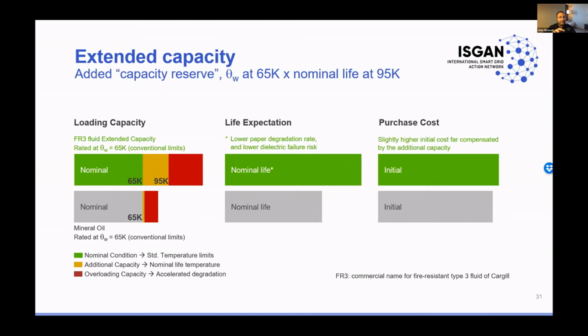The important point here is, as Angelo mentioned, the assessment of the losses in the transformer life considers nominal rated capacity, but the transformer is always dynamically loaded, and a typical average loading will be much lower than 100%. So when we expand the loading capacity, we can increase the average loading, increasing the asset utilization, and bring this closer to the sweet spot, which would be a 50% average loading. That was my portion here. Thanks a lot.